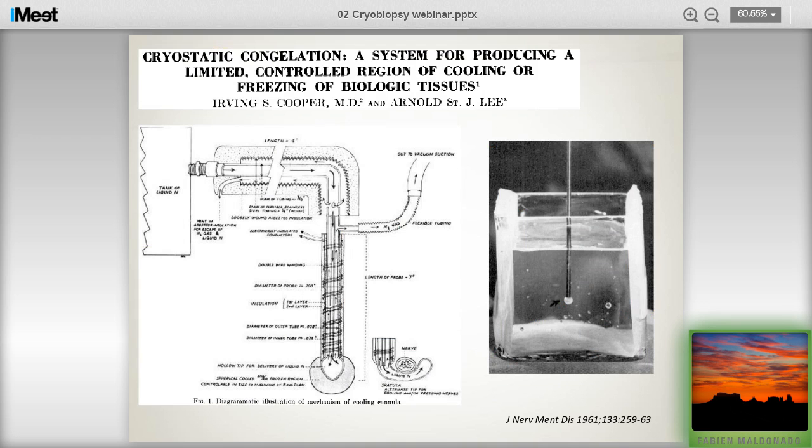And as you know, cryobiopsies have been around for some time. They are essentially probes that were developed to generate very low temperature at the tip. The way this works is, as you know, some compressed gas, which can be nitrous oxide, but more commonly CO2, expands rapidly at the tip, resulting in a profound decrease in temperature, about minus 89 degrees Celsius for the nitrous oxide and minus 79 for the CO2, which I think most of us would be using, so not quite as cold. And then the gas is vented in the atmosphere.